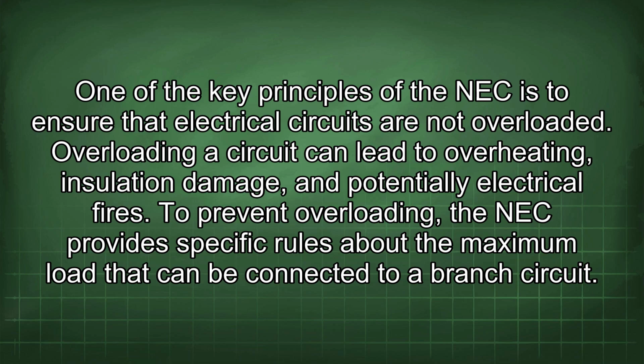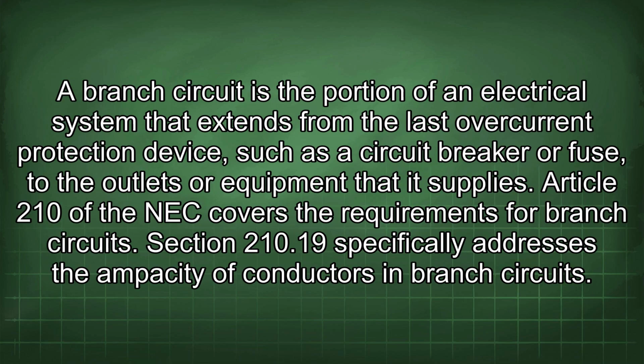To prevent overloading, the NEC provides specific rules about the maximum load that can be connected to a branch circuit. A branch circuit is the portion of an electrical system that extends from the last overcurrent protection device, such as a circuit breaker or fuse, to the outlets or equipment that it supplies. Article 210 of the NEC covers the requirements for branch circuits. Section 210.19 specifically addresses the ampacity of conductors in branch circuits.